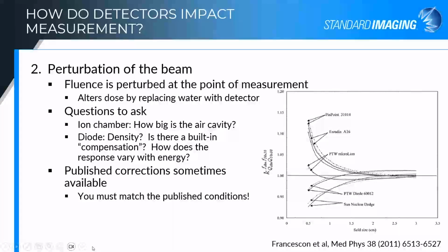So the questions to ask yourself as you're choosing some of these detectors is, with my ion chamber, how big is the air cavity? How much am I decreasing that scatter relative to the full size of my beam? Is that affecting the measurement itself, because I'm no longer getting the lateral scatter out from where that water is being displaced by my air cavity? And for a diode, what's the density of the diode? Some diodes are considered compensated diodes, which means that they usually have a lower density region right next to the higher density diode in order to try and balance the interaction and decrease perturbation that way. Those work fairly well at the energies they're designed for, but sometimes they're not ideal across the board. So you have to be aware, if you have a compensated diode, what was that designed for, and is that going to cause different sorts of perturbations at the other energies or other field sizes where I'm taking it outside the range that it was designed for.